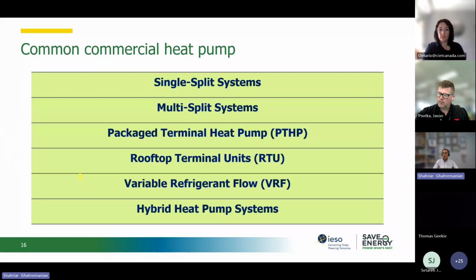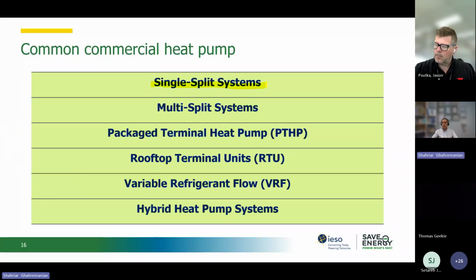The common commercial heat pumps are like this: the single split. I'm sure most of us have seen these for an IT room, for example, which wants an independent cooling system, or for an elevator room. So these are single split systems. Then we go to the multi-split systems, which are also common commercial heat pumps. And then we go to the package terminal heat pumps, which are one unit, mainly seen in hotel rooms. It has everything inside. We just need to cut the wall, put it there, and add a grill on the outside, and that's it. It has everything inside: the fan coil, the heating coil, the cooling coil, the reversing valve, the compressor, everything. Or the rooftop units.